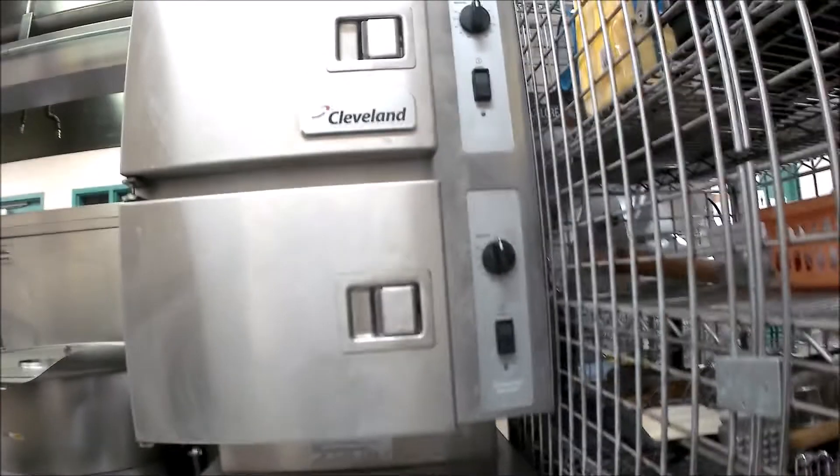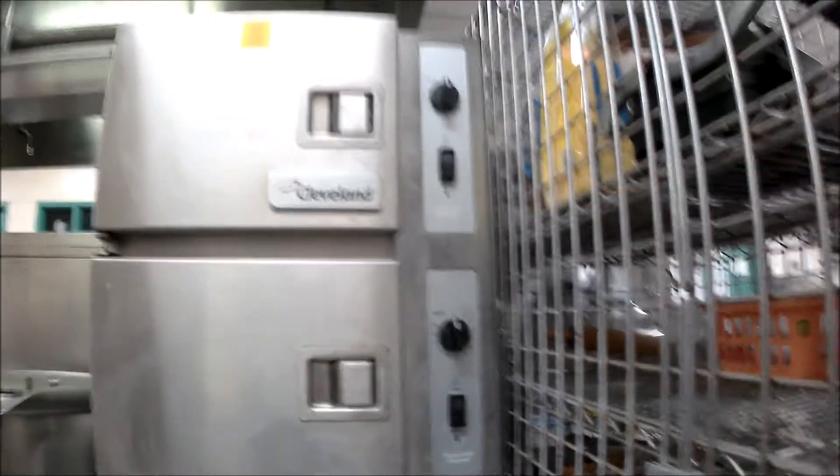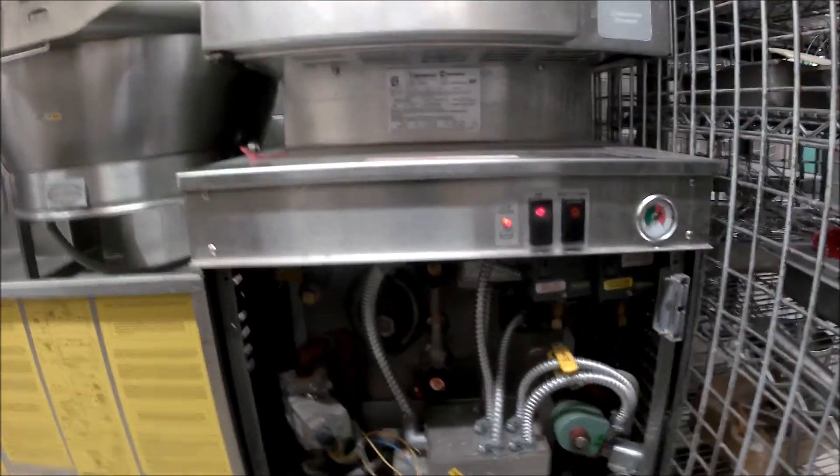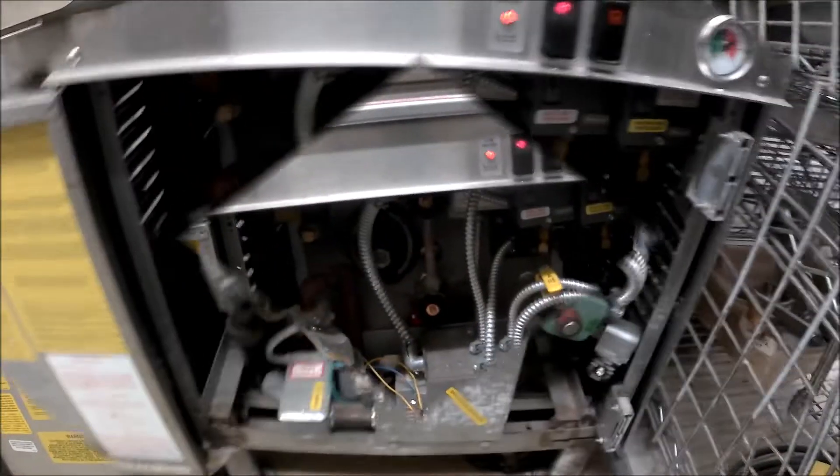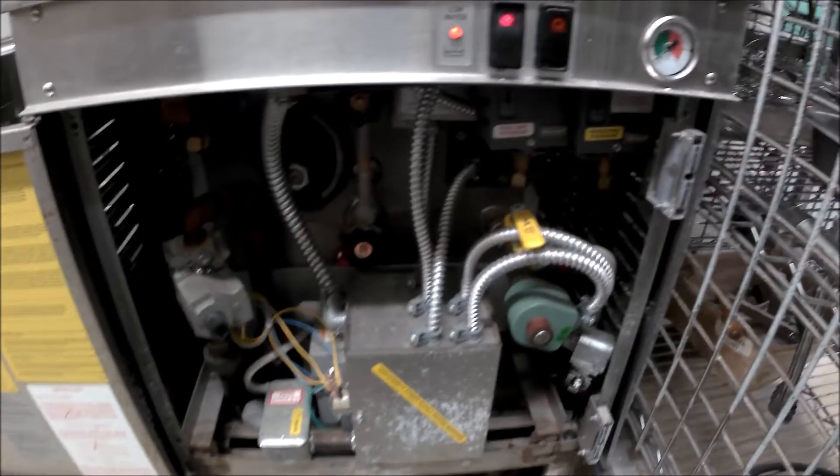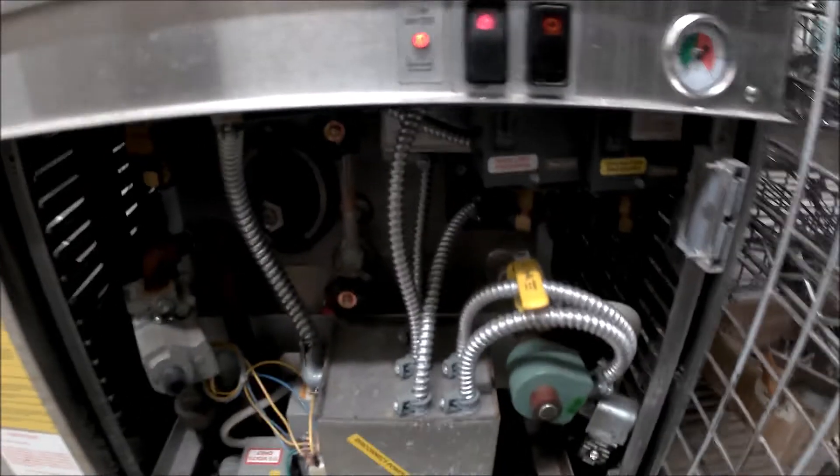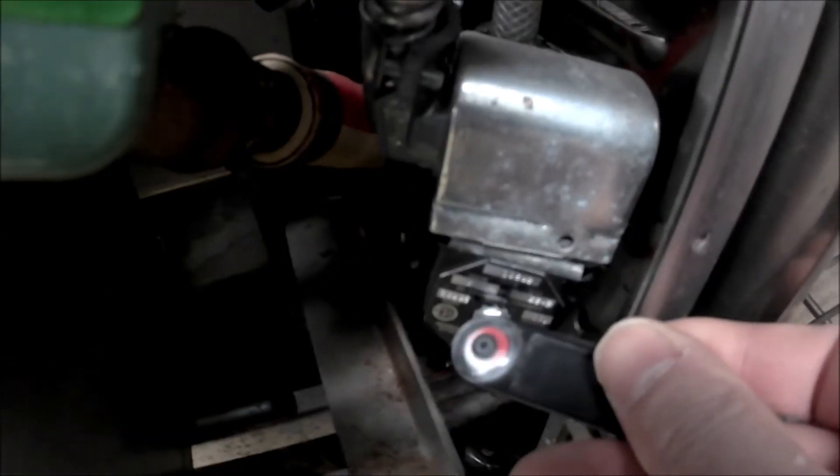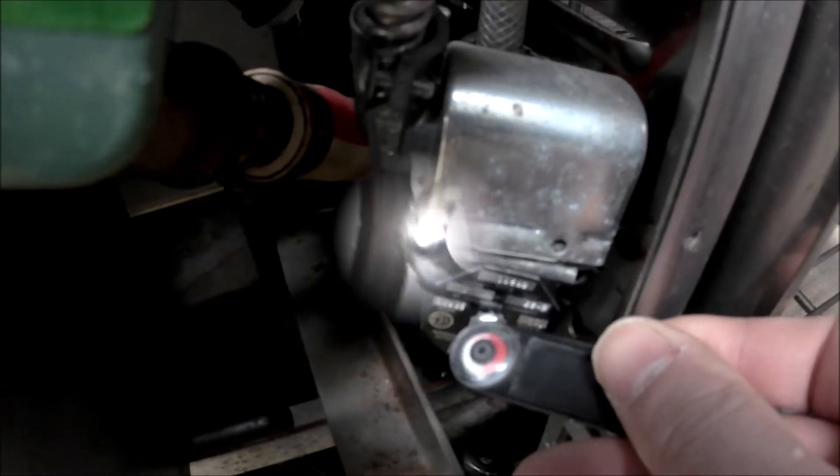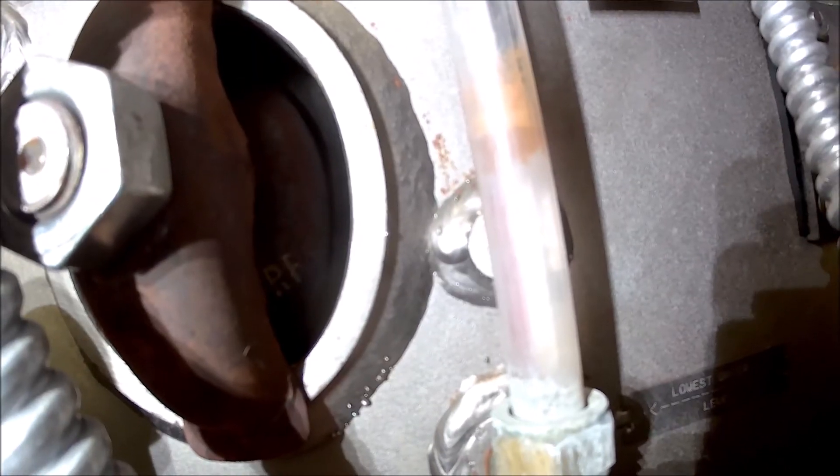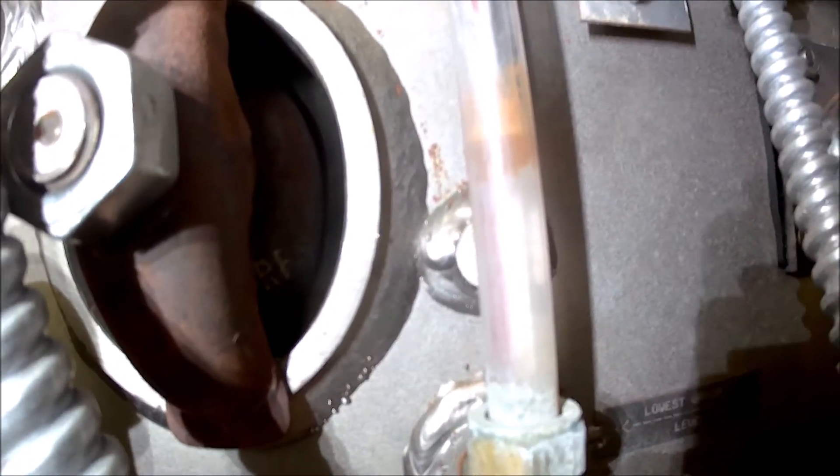We're going to start with all our visual checks first, make sure nothing obvious is happening to point us in the right direction. First thing, are we filling the boiler? Solenoid has power, sight glass is filling up as you can see here.